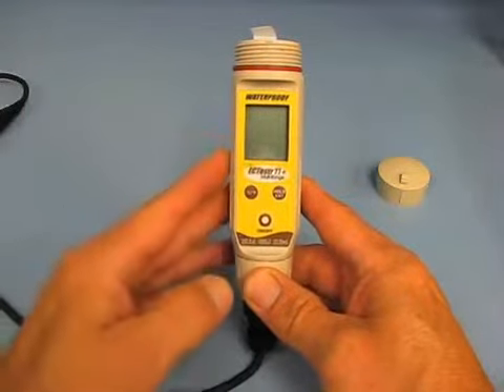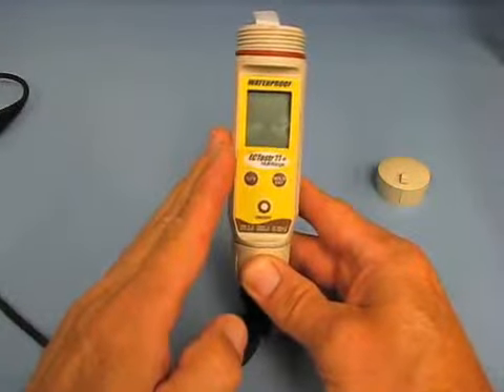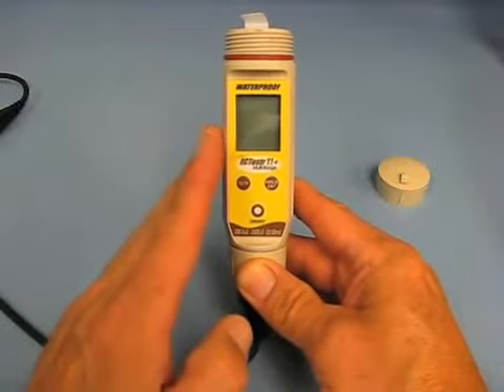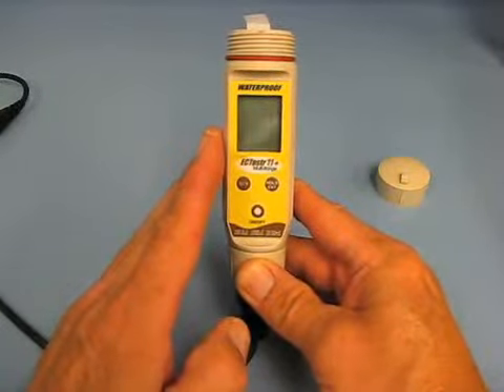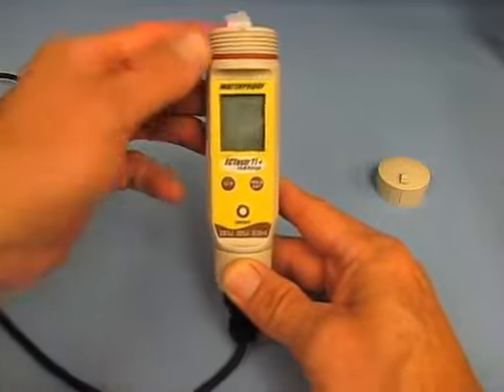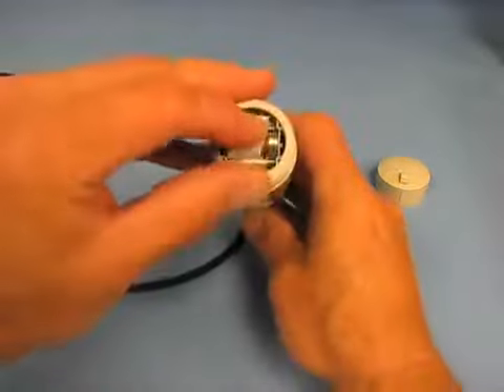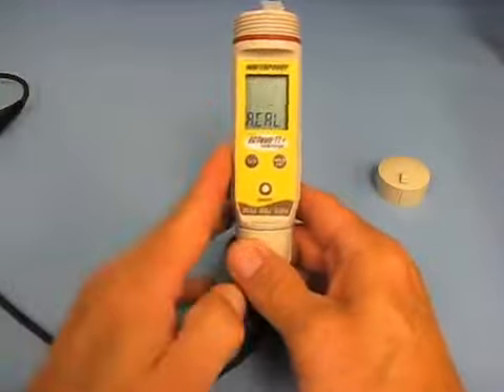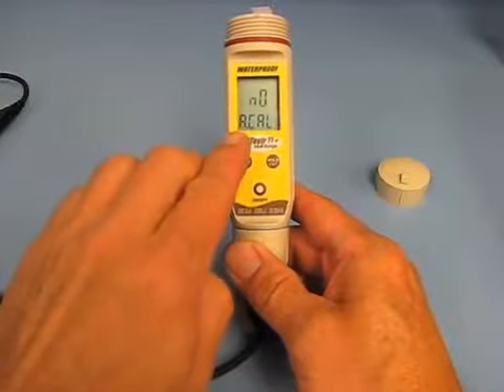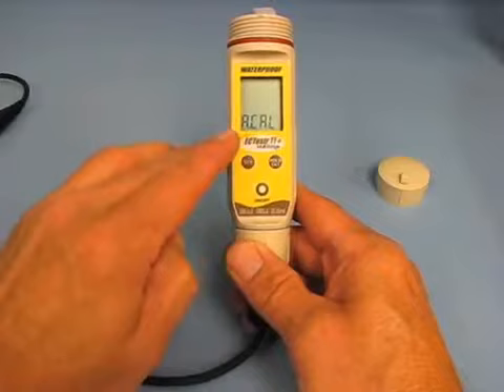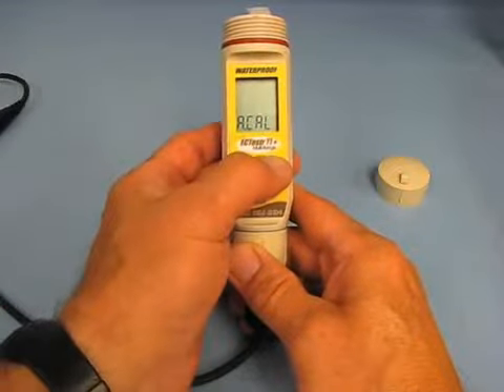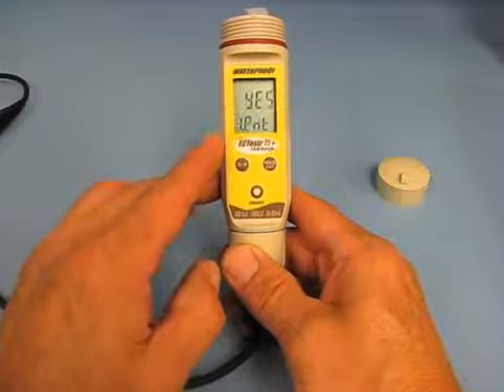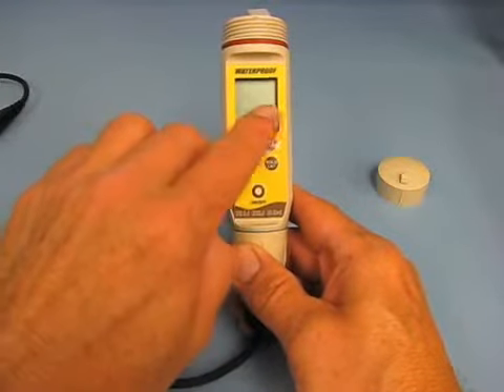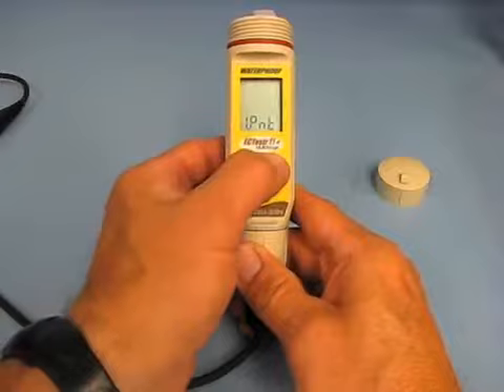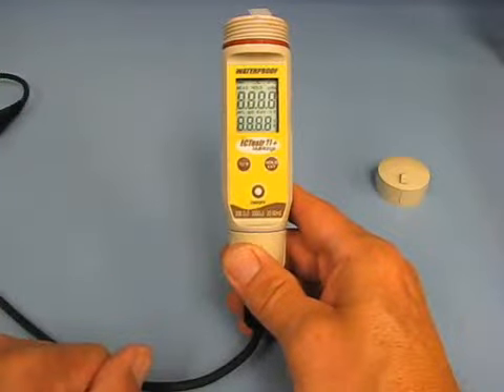There's a small chance that your meter might be set up for a different type of calibration system than what we need for what is described in this video. So let's make sure your meter is set up correctly. To do so, you hold the increment button down, that's the right button, and press the on-off button. This will tell you what kind of calibration mode the meter is set up for. Right now it says auto calibrate no. That's exactly what we're looking for. And then we'll press enter. That'll take us to 1-point calibration. We want it to say yes. And we press enter to go ahead and fix those numbers.